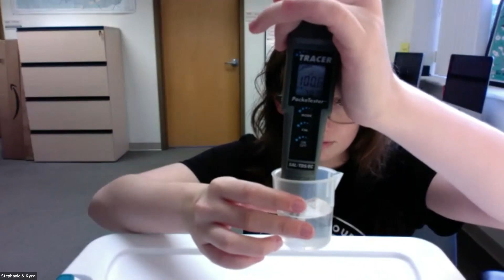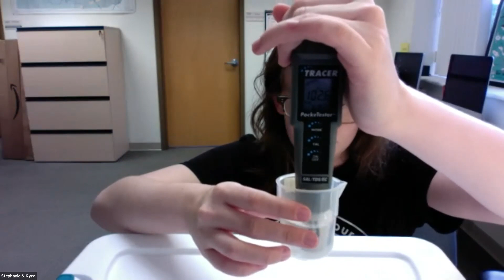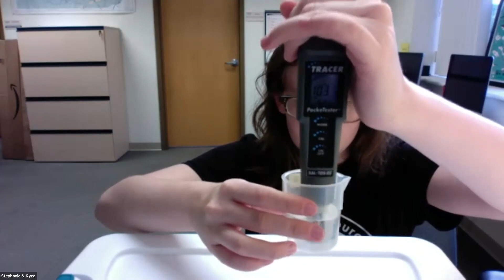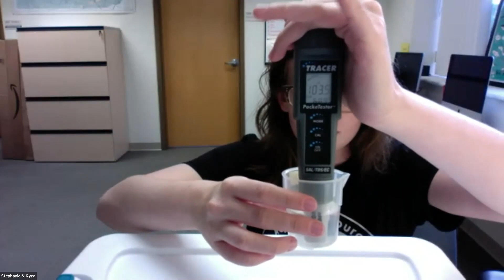And while I wait for that to stabilize for Kyra's meter, I will also share the acceptable range of the meter. If your number is above 200, it will be a whole number. And if it's below 200, there will be a decimal point to the nearest tenth. So be sure to look at your meter closely and make sure that there's not a glare or anything to make sure if there's a decimal point or not. Looks like Kyra's is still going up a little bit. Hey, and Kyra, you have shaded your meter screen with your hand. There you go. Thank you. Perfect.